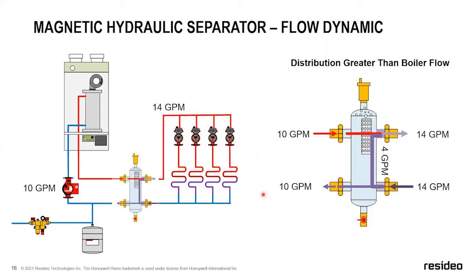So in this example, we're driving more flow on the system side. As the water comes in at 10 gallons a minute, that pump is still going to create that pressure differential, which is going to bring 10 back, but we're going to have more flow taking place over here from all the pumps. So that differential from 14 to 10, you've got 4 gallons a minute that's going to come up through the middle and back in to come through here.